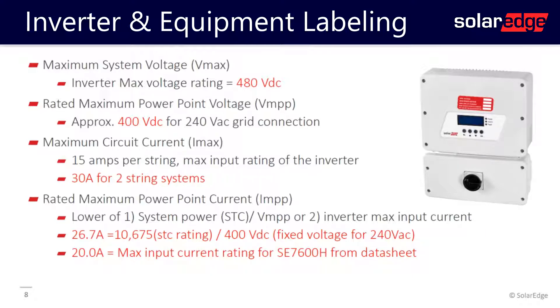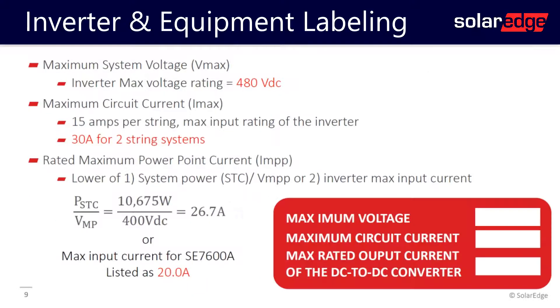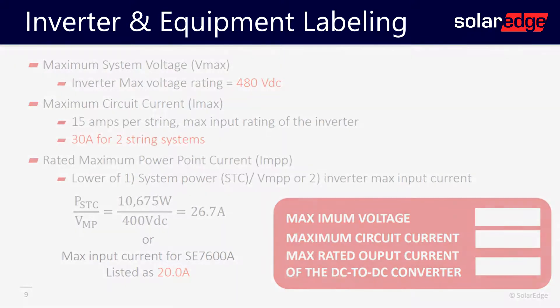The inverter will current limit the system and never exceed 20 amps. In the 2017 code, this label requirement changed just a bit. We are no longer required to put the VMP on the label, so all we need is VMAX, IMAX, and IMP.